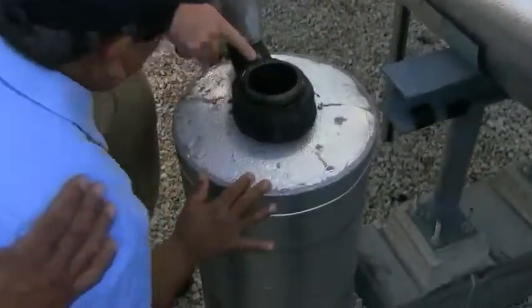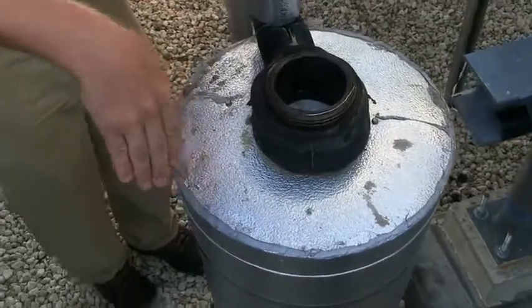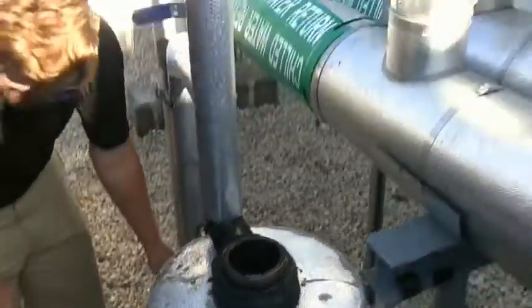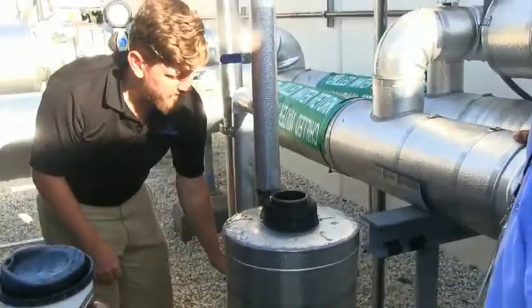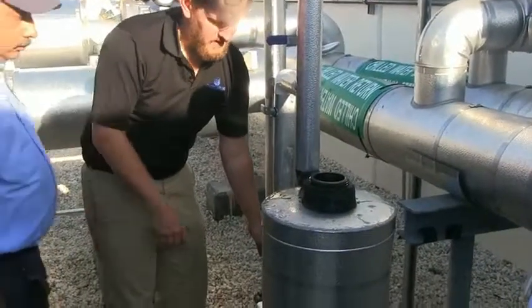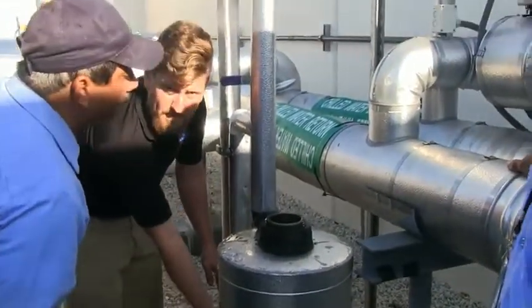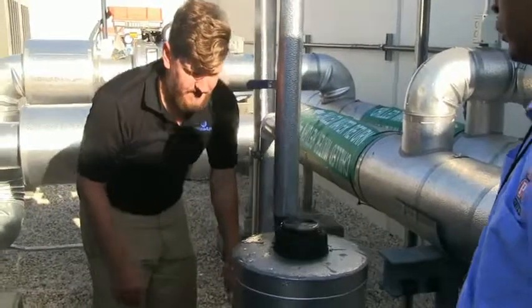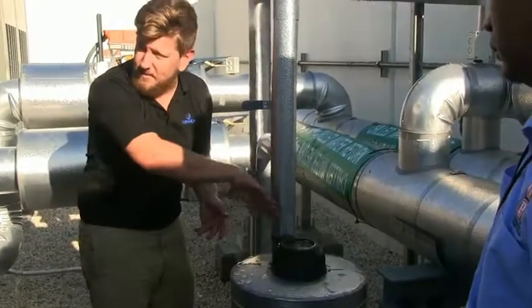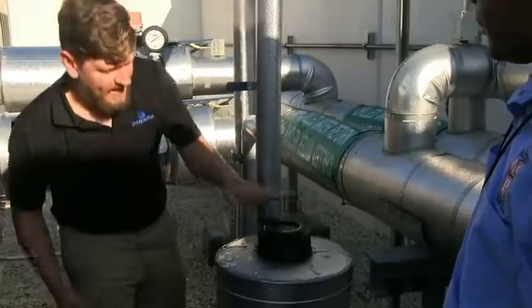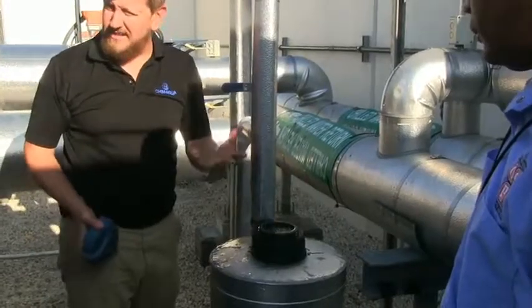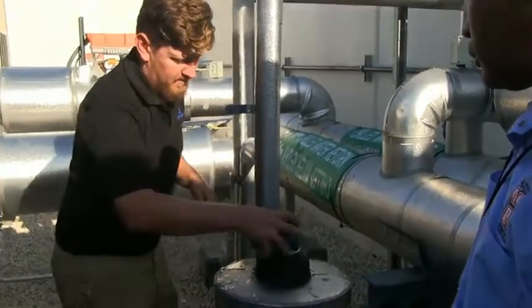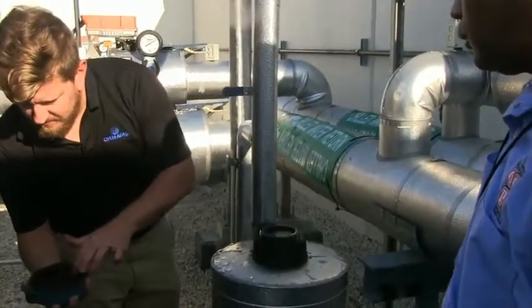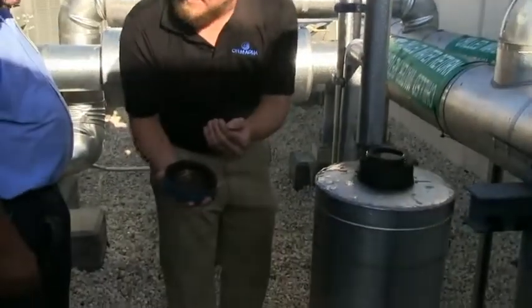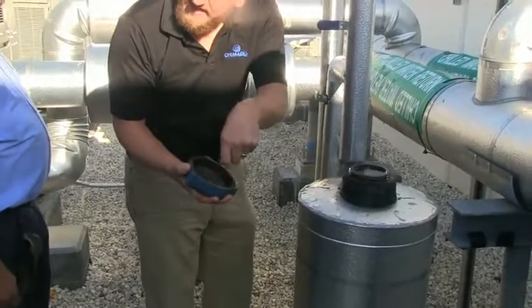Get below the hole, that means the water's going to go through the filter. All right? At that point, you can open up either valve, but I open up the bottom one because that'll bring the water up in a smoother way instead of spraying yourself with it. Try to get it up here. You don't want too much oxygen introduced to the system. Make sure your seal right here is seated nicely. Sometimes it'll start to pop out. You just slide it back in. You can get it with a screwdriver.